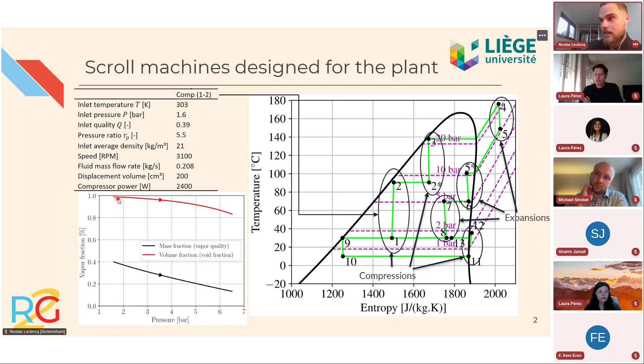And if you link a mass fraction, which you can see here on the diagram, with the volume fraction, which is the real volume taken by the liquid and by the vapor, at the inlet of the machine you can see that it's not so low. For instance, here we have 40% of vapor in mass, but we almost have 100% of vapor in volume, because the density of the liquid phase is way higher than the density of the vapor phase. This is just something that I wanted to mention. So we still have a lot of vapor in the machine.